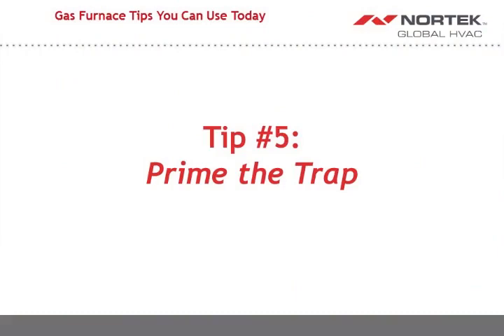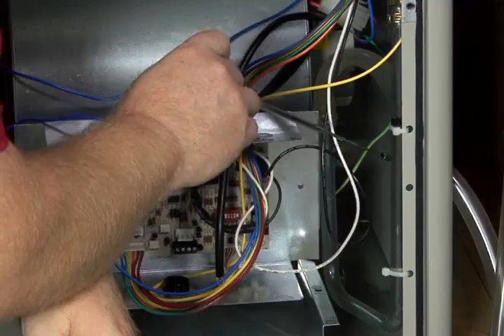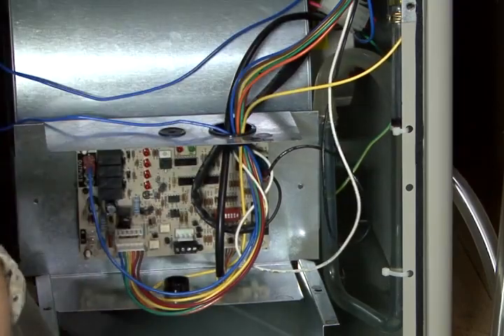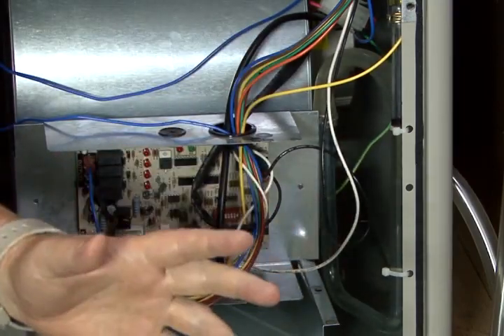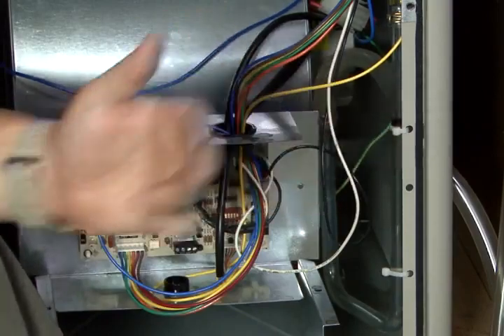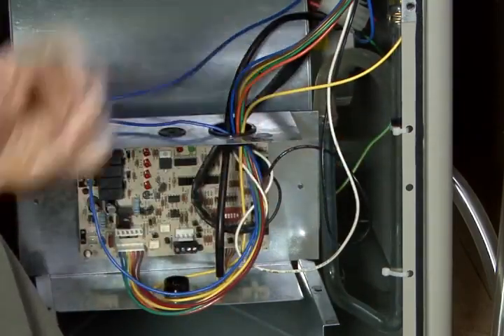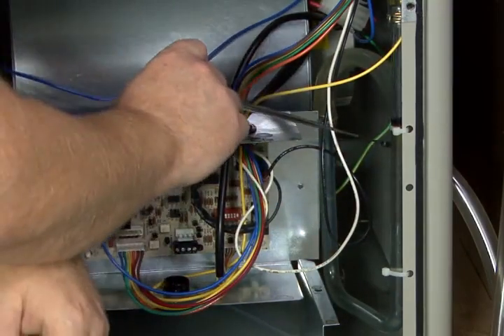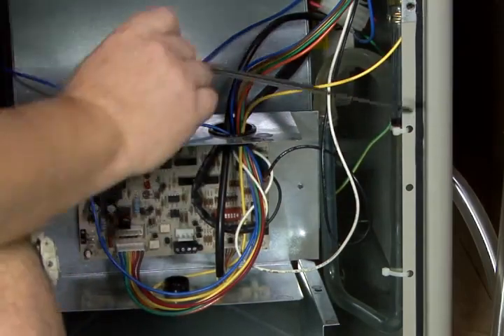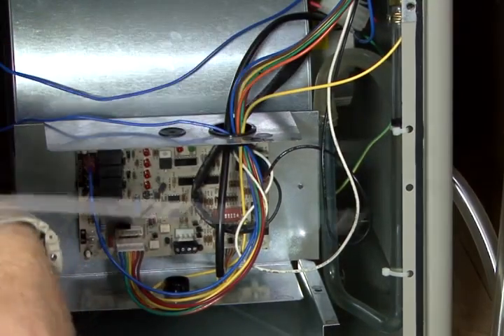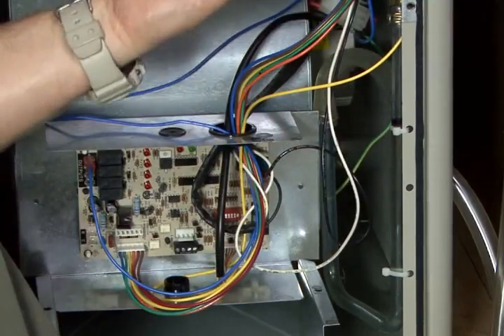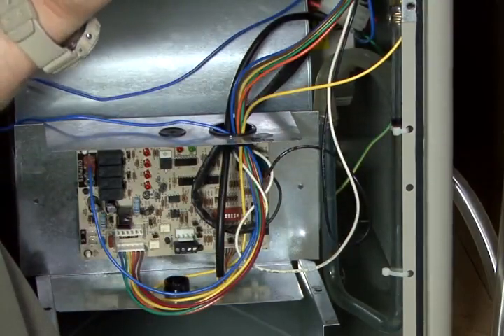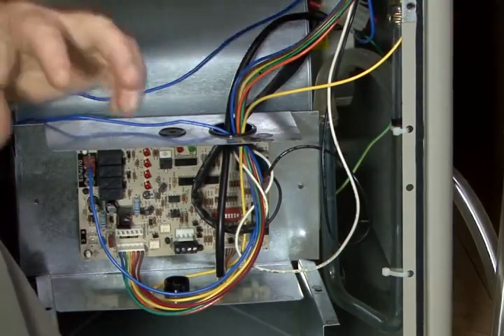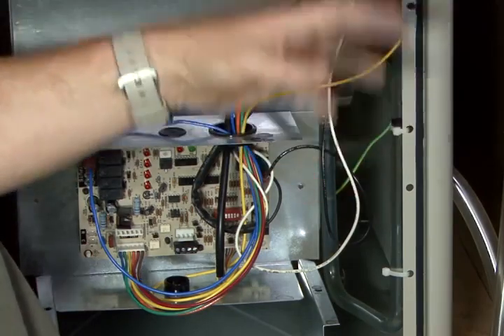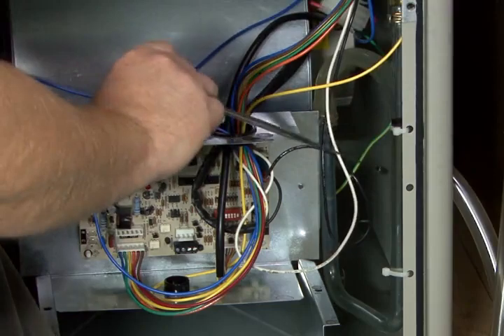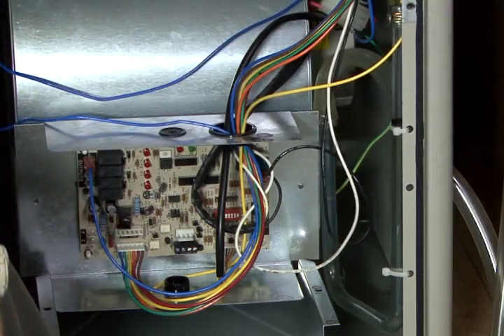Tip number 5. Prime the trap. Right there. When you open up a brand new high-efficiency gas furnace and you remove the blower compartment cover panel, right over here on the side of that compartment, you're going to see a clear plastic J-tube trap. When you do installations on high-efficiency gas furnaces, before you start that furnace up and begin to do your checkout procedure, you want to make sure that you prime that trap with water.